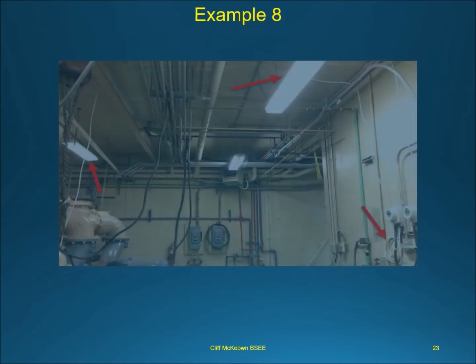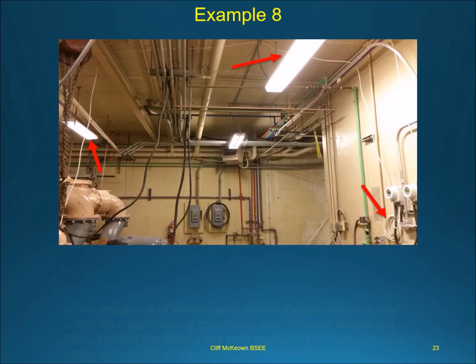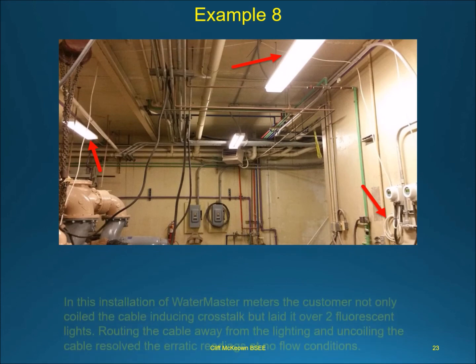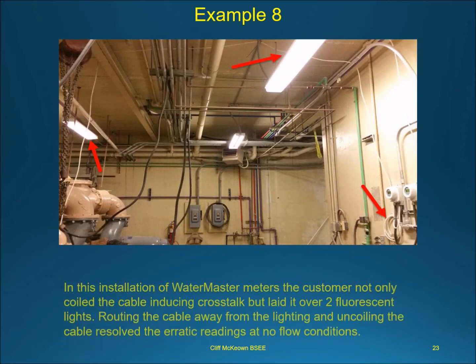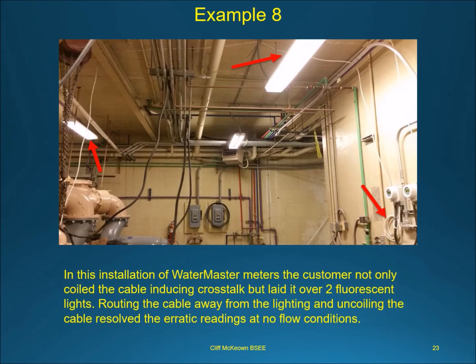In this installation of Water Master meters, the customer not only coiled the cable — inducing cross-talk — but laid it over two fluorescent lights. Routing the cable away from the lighting and uncoiling the cable resolved the erratic readings at no-flow conditions.